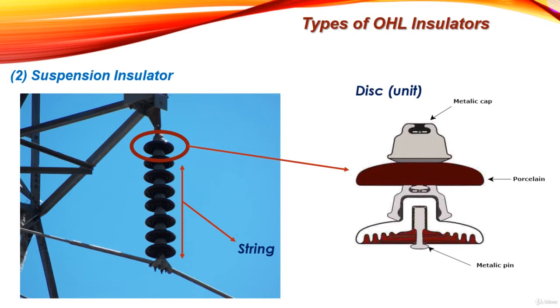Each unit consists of a metallic cap, porcelain as the insulator material, and a metallic pin. The conductor is suspended at the bottom end of the string by means of a metallic pin, while the other end of the string is secured to the cross arm of the tower by means of a metallic cap. The metallic pin and cap are also used to connect the units with each other to form one insulator string.